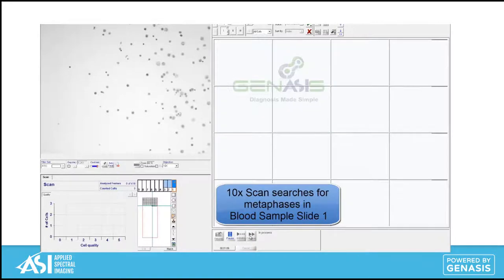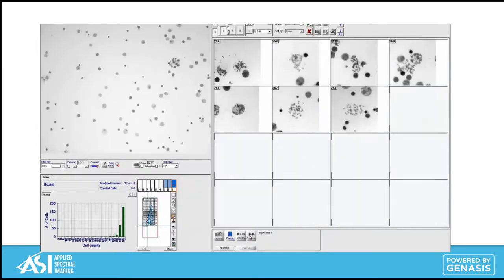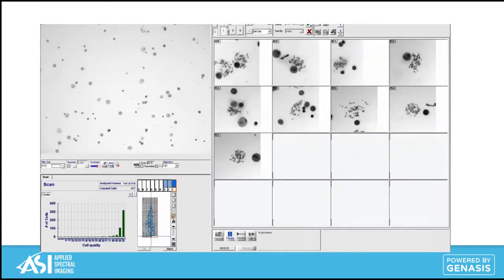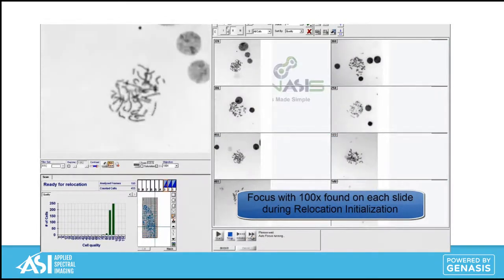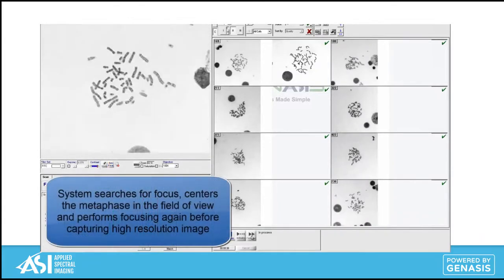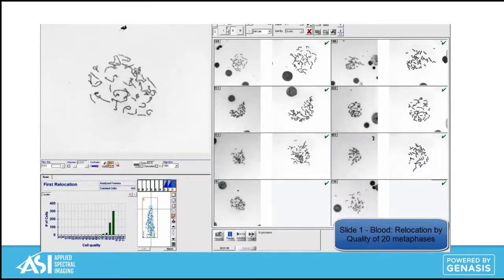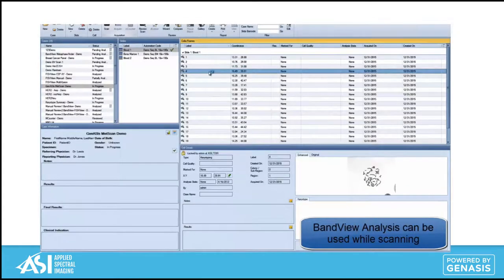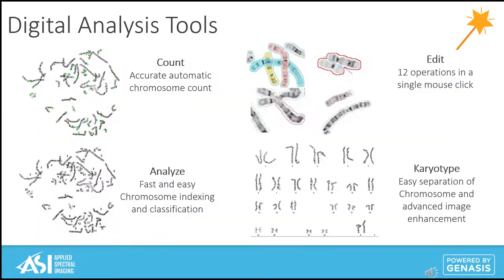For metaphase scanning, utilizing an automated microscope, nine-slide stage, and oil dispenser, MetScan begins by performing a low-mag pre-scan to identify the cover slip and cell colonies, then performs a 10x scan to capture the best metaphases in a relevant slide region, recording their location. Labs have the ability to allow either the algorithm or the user to select the cells which get recaptured at 100x. After selection, the system relocates back to these cells where the camera refocuses and captures the image. As soon as the first image is captured, the technologist can open up BandView to begin analysis as the system continues scanning. During analysis, our magic tool performs up to 12 operations with one single mouse click, allowing the user to accurately count, cut, extend, join, or separate overlapping chromosomes.